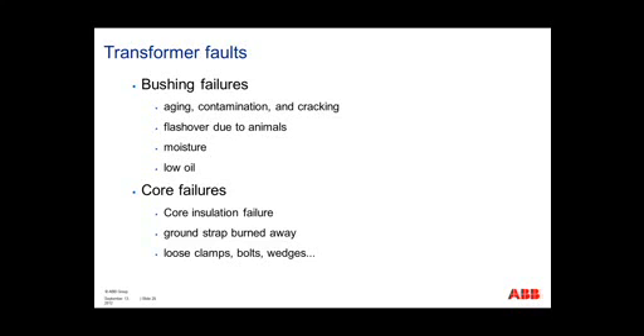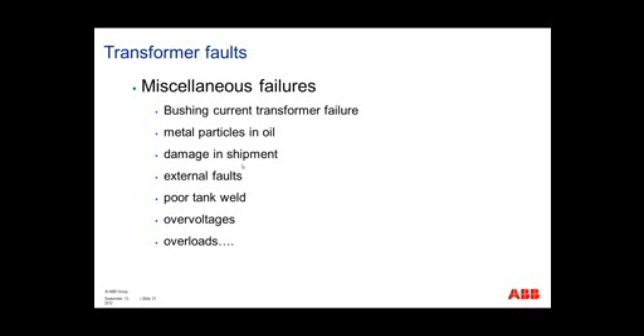You could have bushing failures. Bushing failures are contributed to by aging, contamination, cracking from earthquakes, shotguns, whatnot. You could have a flashover due to an animal, moisture, low oil. These bushings are oil filled, so if you have a drop in your oil in the bushings, you could have a flashover. Core failures. Core insulation failure, your ground strap burned away, loose clamps, bolts, wedges, etc.